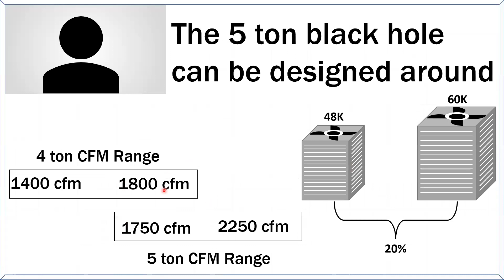And it's because most systems were here, right? And when most systems were here, there weren't gaps. There's this itty bitty little one. You can close that gap with airflow. You can adjust your CFM, right? And there's one here, but again, adjust your airflow, play around with some coil matches, and you can usually close that gap. And here, we're so large that the airflow ranges actually overlap between 4 ton and 5 ton. So you can get huge swings in capacity just by manipulating some of the things you have control over. But down here, we got problems, right? If 4 ton CFM is 1,400 to 1,800 and 5 ton CFM is 1,750 to 2,250, assuming 350 to 450 per ton, you actually have an overlap here. So closing this gap really isn't very hard.